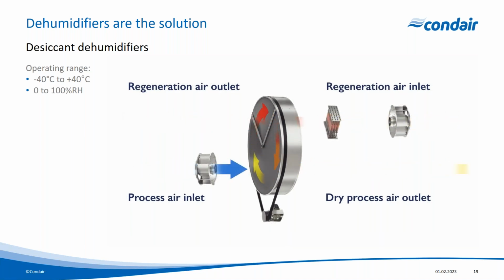Now, cleverly, because we're capturing water in its gaseous phase, we don't need to worry about freezing. So we can operate between -40 and +40 degrees C, and between 0 and 100% RH. So it's a pretty good way of removing moisture from a chill store or a freezer store.